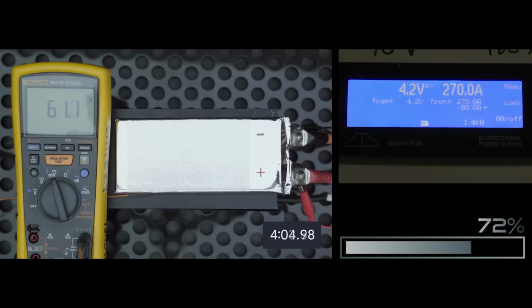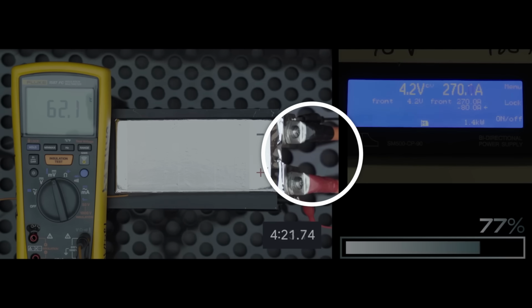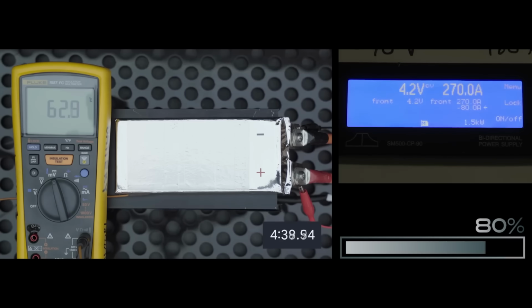The first thought I had is if you look at the wires going into the negative and positive terminals, those wires aren't particularly thick. But think about this: to run 270 amps you'd need like 4/0 cable, which is really, really thick — at least to maintain 270 amps for long periods of time. Those wires are clearly not that. But if they're just doing a quick test for 5 minutes, they could probably tolerate those wires getting hot for a while.